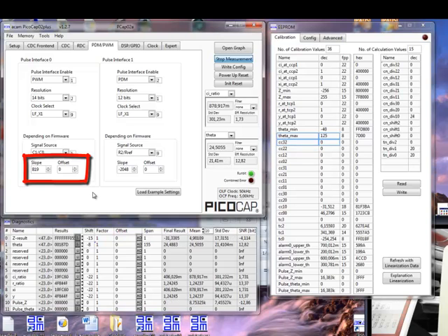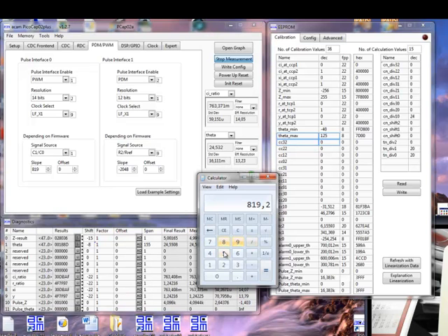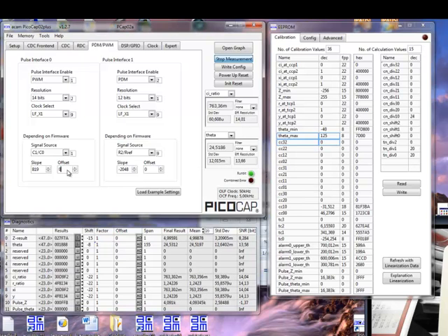And this gives me my slope of 819, which I fill into this field. And now I basically also need to calculate the offset, which happens the same way. I have an offset of 5 PSI, since this is my lower range limit, and 5 PSI times the configured slope of 819 gives me now my offset of 4,095 to fill in to this field.